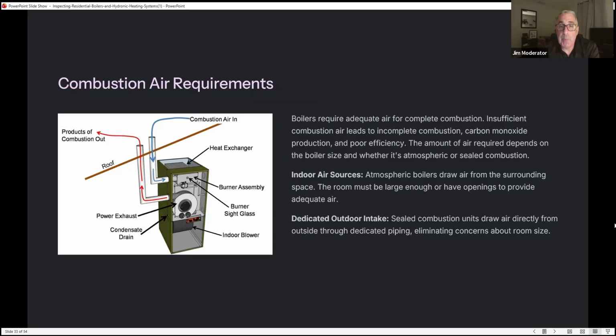Combustion air requirements. Boilers require air for complete combustion. Insufficient combustion air leads to incomplete combustion, carbon monoxide production, and poor efficiency. The amount of air required depends on the boiler size and whether it's atmospheric or sealed combustion. Indoor air sources: atmospheric boilers draw air from the surrounding space. The room must be large enough or have openings to provide adequate air. Dedicated outdoor intake: sealed combustion units draw air directly from outside through dedicated piping, eliminating concerns about room size.